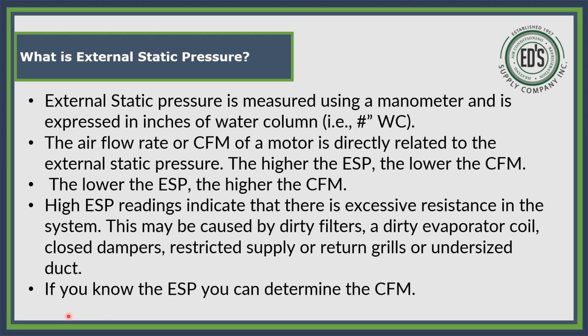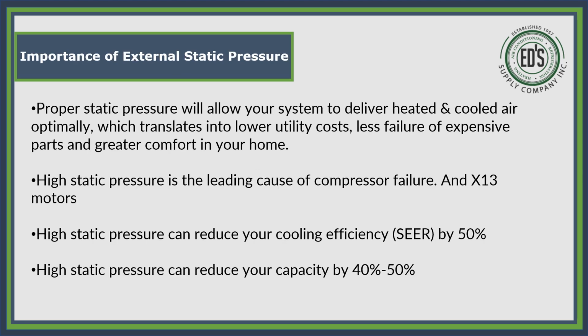And now I'm going to repeat that. If you know what your external static pressure is, you'll be able to determine what the CFM is. Just because you have a 2-ton unit doesn't mean it's always going to blow out 800 CFM. Keep that in mind. Proper static pressure will allow your system to deliver heated and cooled air optimally. This translates into lower utility costs, less failure of expensive parts, and greater comfort in your home.